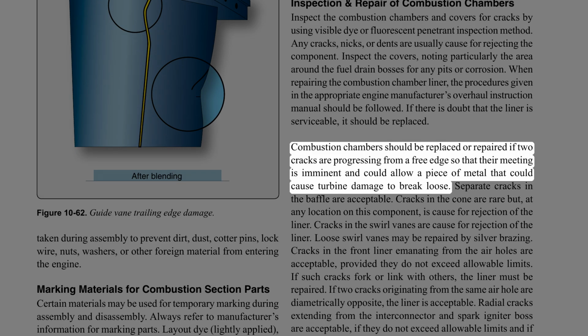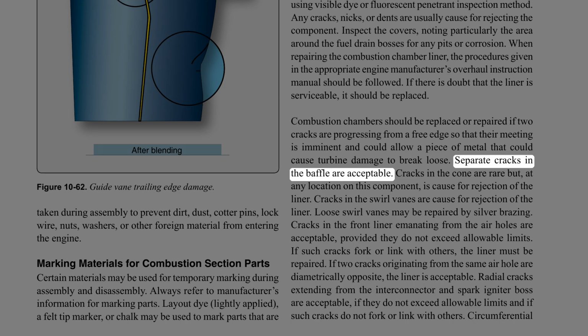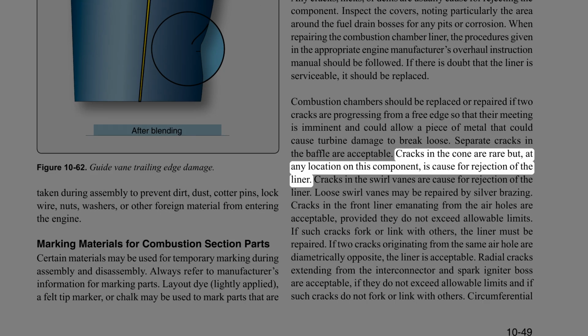Combustion chambers should be replaced or repaired if two cracks are progressing from a free edge so that their meeting is imminent and could allow a piece of metal that could cause turbine damage to break loose. Separate cracks in the baffle are acceptable. Cracks in the cone are rare but, at any location on this component, are cause for rejection of the liner.